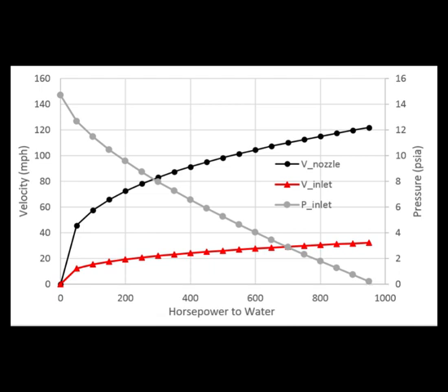So this explains why you can cavitate when you're sitting in nice, calm water. Basically, the water rushes into the pump and the pressure decreases. And when the water reaches the impeller, the pressure decreases even further, possibly to the boiling point. Appropriate impeller design can minimize this boiling. And if it's limited to just the front edge of the impeller, then you may not notice it at all. Or you may experience it as what is referred to as a flare, which is just a partial cavitation.